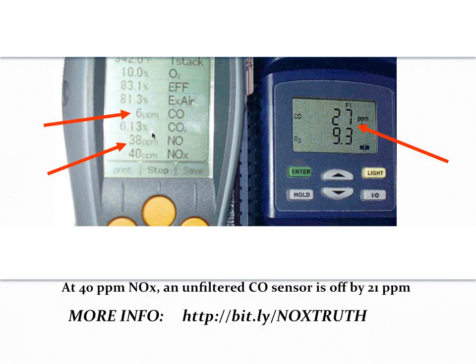Most manufacturers either have built-in NOx filters or provide them outboard. We do sell a brand we've sourced at TrueTech. It's a very cost-effective brand called Correct Measurements. I believe it's $39.95, including free shipping. So if you don't have one in your meter, you can splice it into the sampling line, the sampling hose, and use it for your CO reading to cancel that NOx. If you want to learn more about it, take a look at that bit.ly link down at the bottom of the page, bit.ly/NOxTruth, all uppercase, or attend the session. We'll be doing the webinar live in a few days regarding CO air-free measurements, and we'll get into this too at that point.